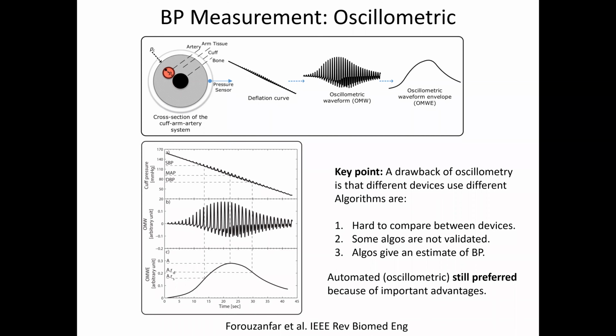And they estimate BP. So I talked about how Korotkov sounds delineate the systolic and diastolic. And so those are very specific, easily recognizable in most cases anyway, discrete phenomena, whereas you don't have that with oscillometry. And because of that, you do have to make sure that you're using a device that is validated, because that means that in part that algorithm has been validated. And you can't really compare between the devices or expect them to be exactly equivalent, because those algorithms can be very different. Next slide, please.